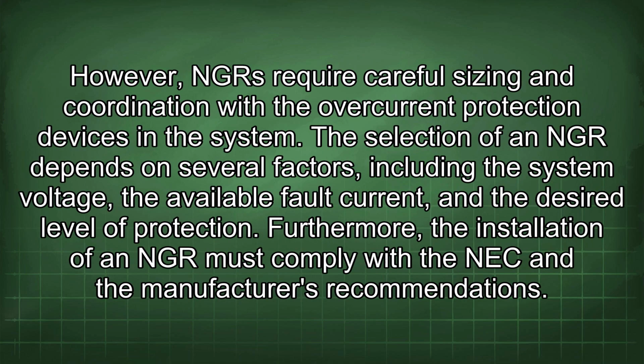However, NGRs require careful sizing and coordination with the overcurrent protection devices in the system. The selection of an NGR depends on several factors, including the system voltage, the available fault current, and the desired level of protection. Furthermore, the installation of an NGR must comply with the NEC and the manufacturer's recommendations.